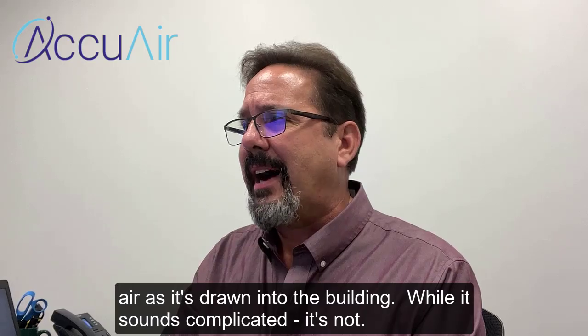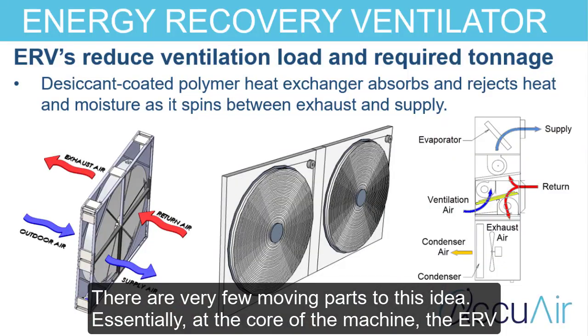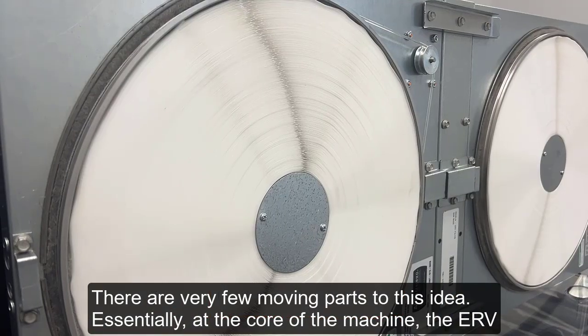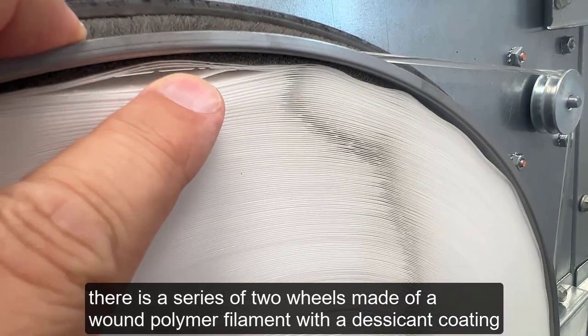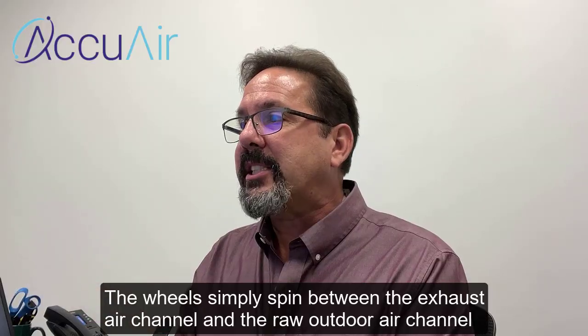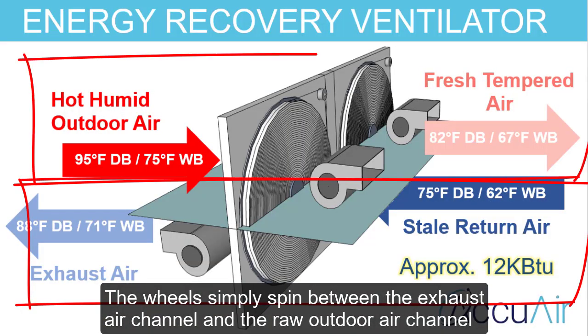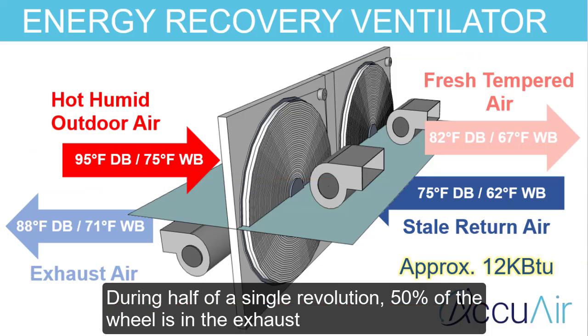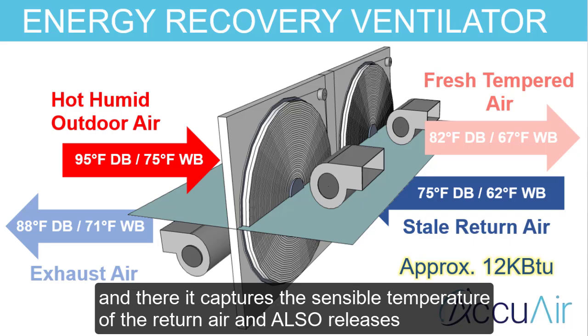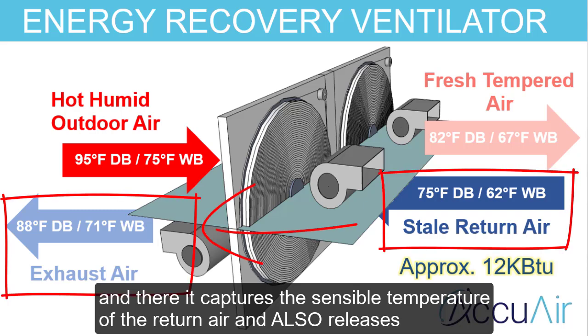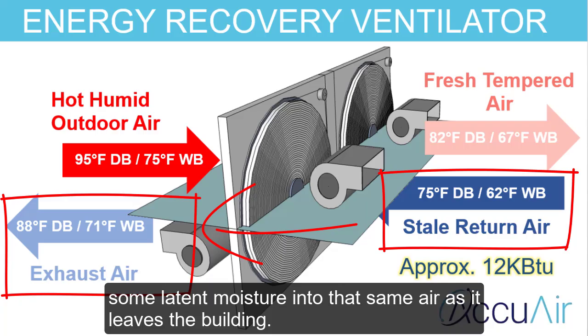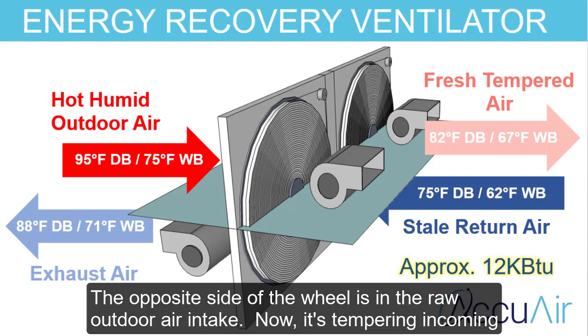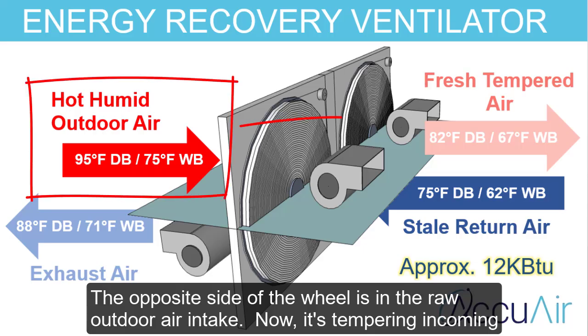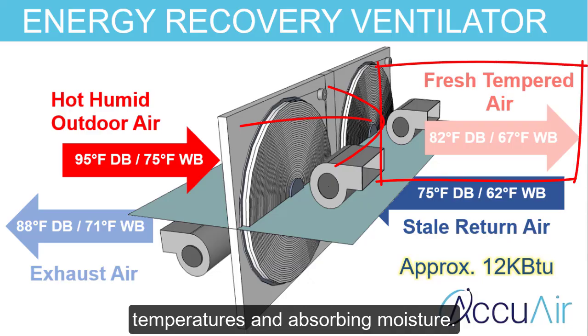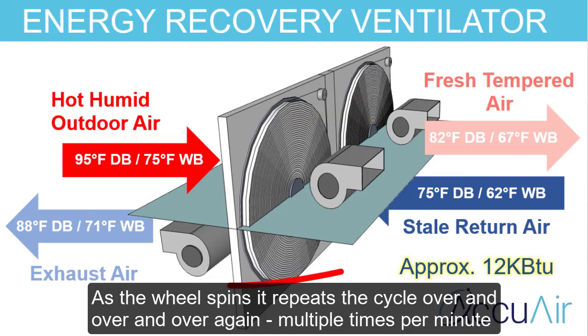While it sounds complicated, it's not. There are very few moving parts to this idea. Essentially, at the core of the machine, the energy recovery ventilator is a series of 2 wheels made of a wound polymer filament with a desiccant coating. The wheels simply spin between the exhaust air channel and the raw outdoor air channel. During half of a single revolution, 50% of the wheel is in the exhaust. And there it captures the sensible temperature of the return air and also releases some latent moisture into that same air as it leaves the building. The opposite side of the wheel is in the raw outdoor air intake. Now it's tempering incoming temperatures and absorbing moisture. As the wheel spins, it repeats this cycle over and over and over again, multiple times per minute.